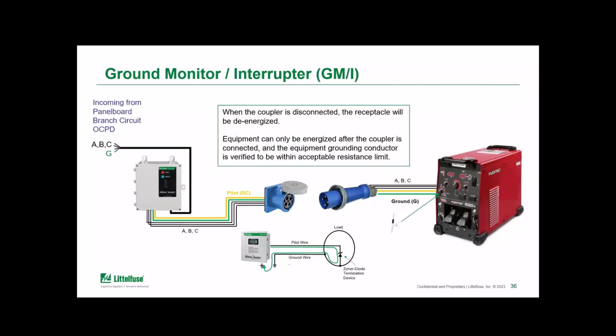I think I've reiterated this point many times, but here is just one final way to talk about it with the ground monitor interrupter circuit. When you look at the safety of, let's say, receptacles or drop cords that are perhaps sitting in a facility and not being used or disconnected, the equipment grounding conductor is open. And so that means that if this was a 480 volt or 600 volt receptacle or cable and was protected by a special purpose GFCI, it would be in the trip state because the grounding conductor would be open circuit.